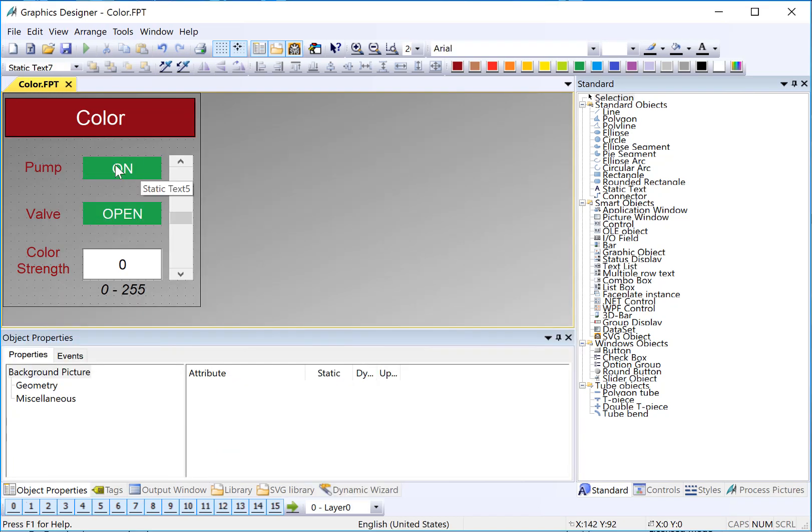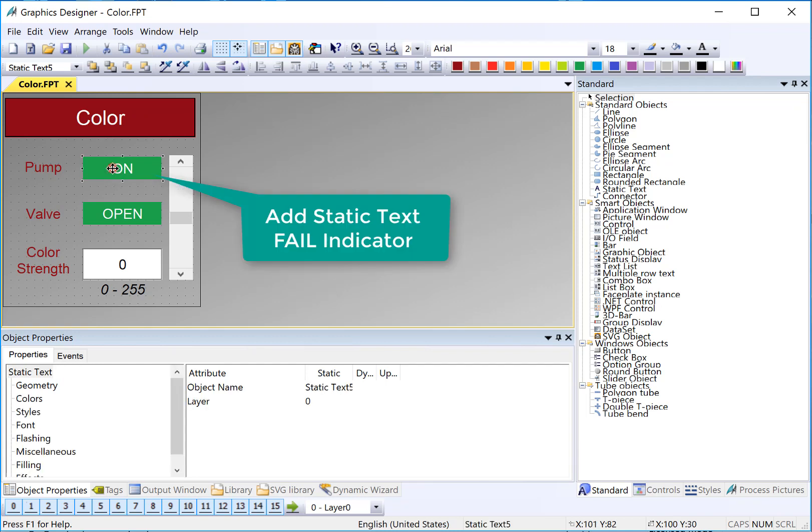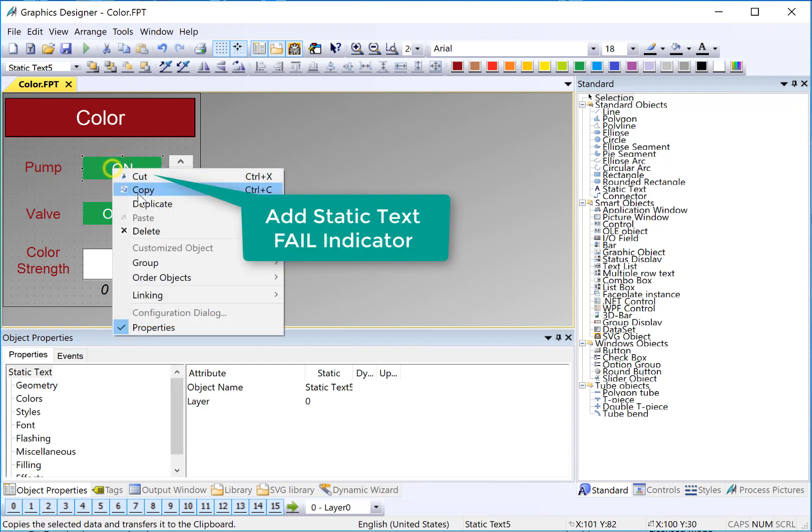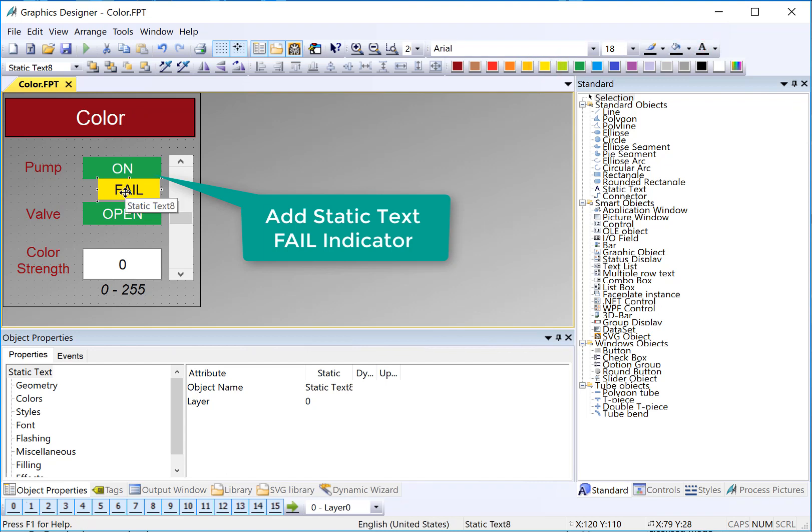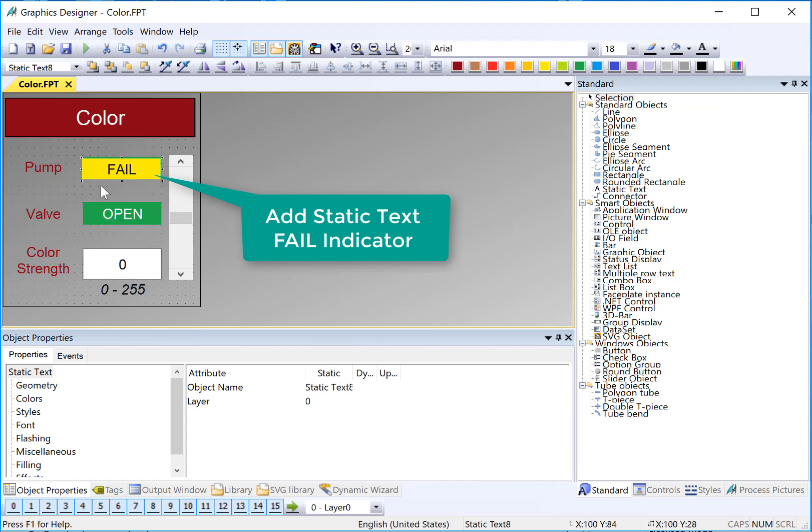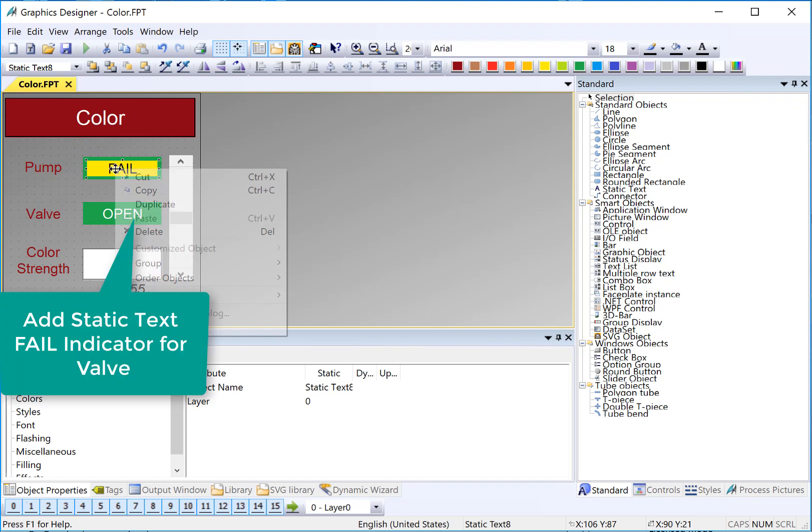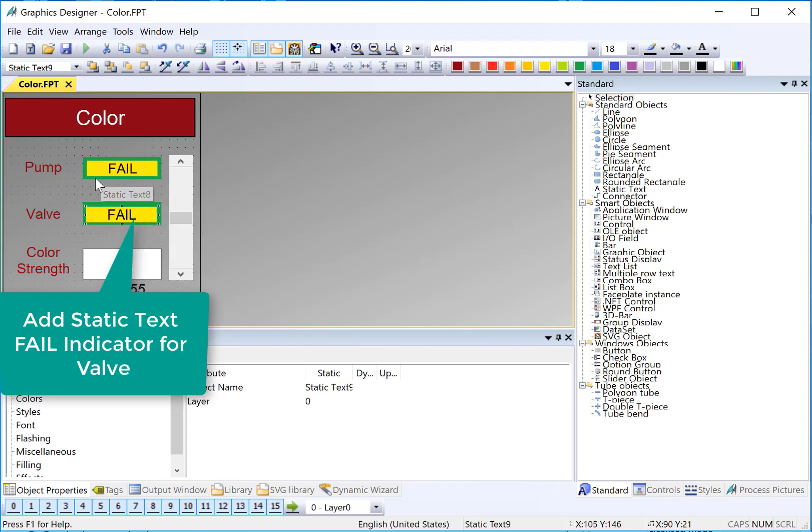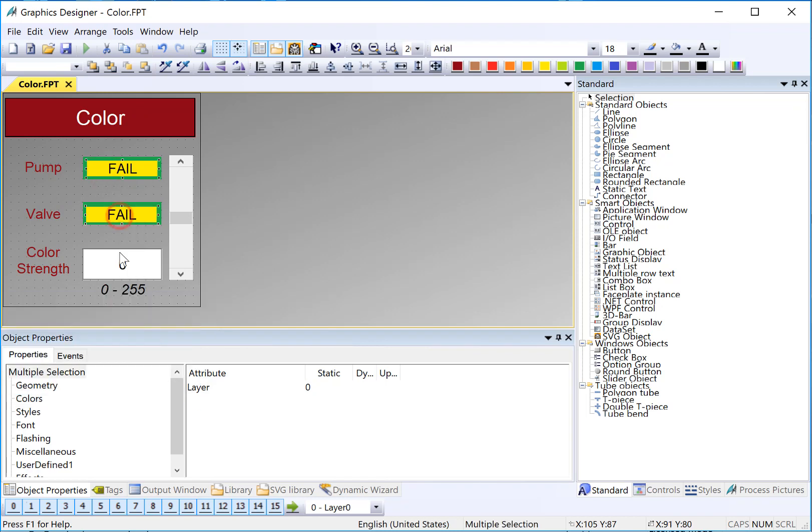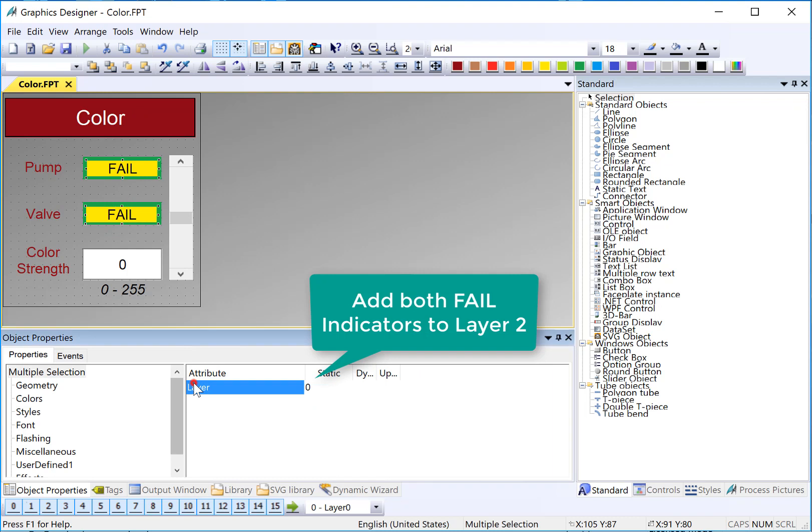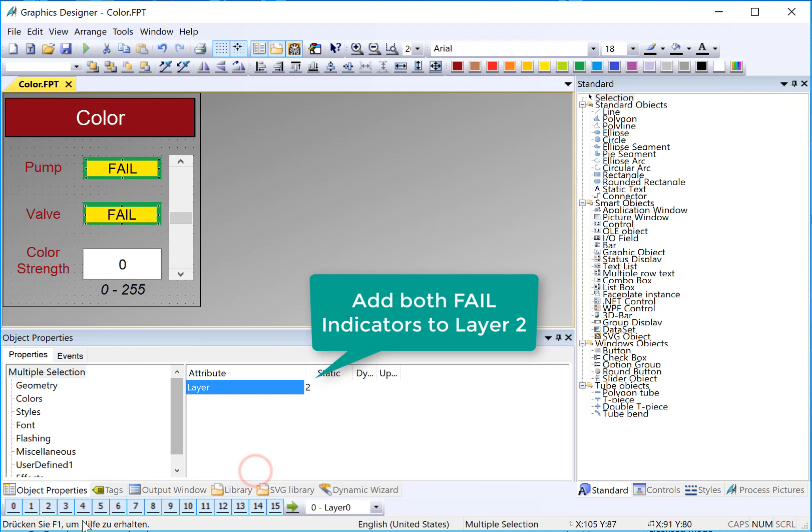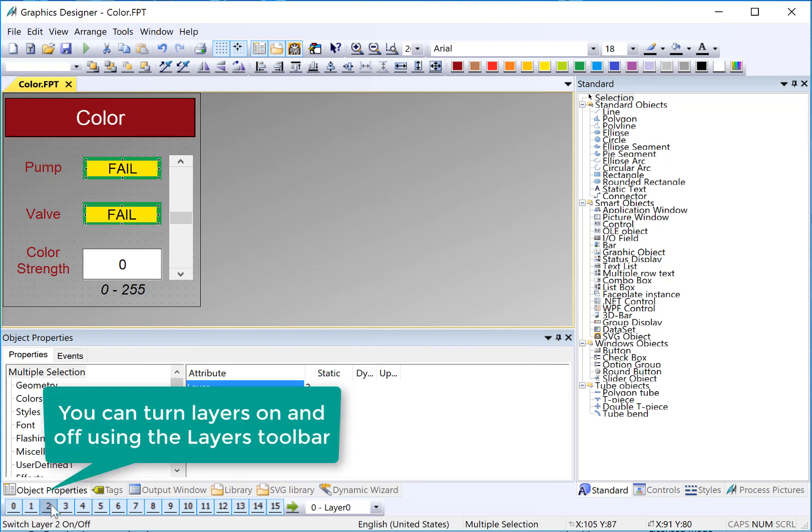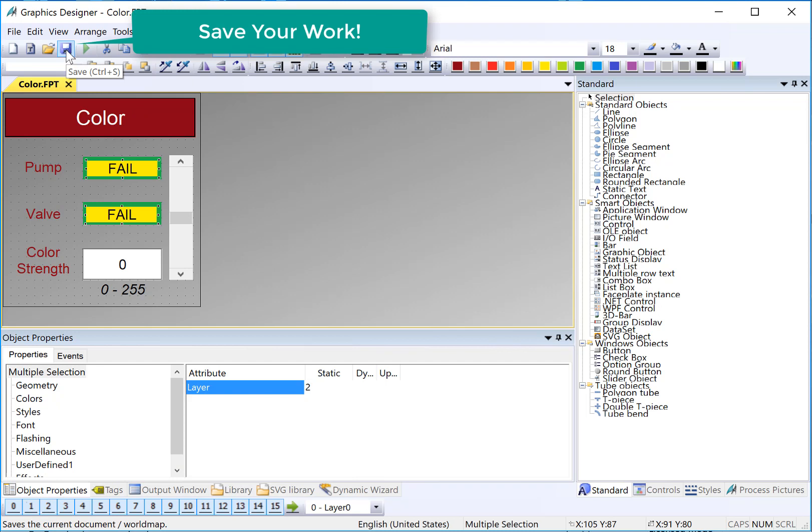Lastly, we want a fail indicator. And so I'll just duplicate one of these and make it slightly smaller. It's going to say fail. So we will give it a cautionary color. And the idea here is it's just going to overlay this if the fail condition for the pump is there. So we'll do it like that. And then I will duplicate this as well. When we're trying to configure the status indicators, these are going to get in the way. So I'm going to select both my fail indicators and I'm going to put them on a different layer, say layer 2. What this means is I can go down to my layers bar and turn them off so that I can get to them. So I am going to save my work.